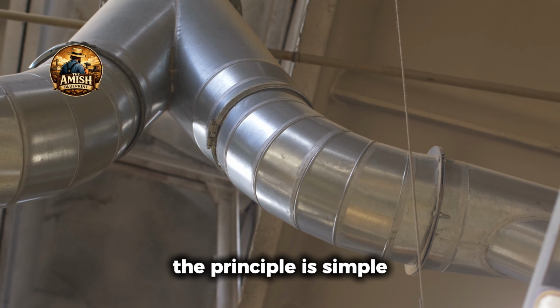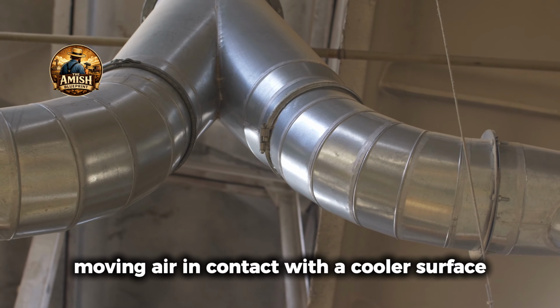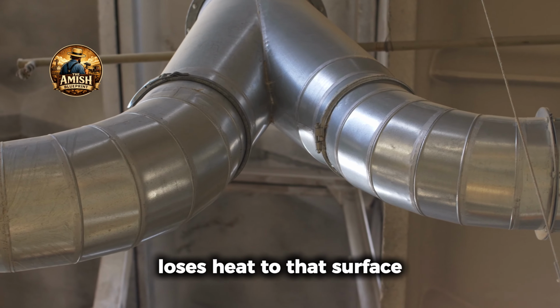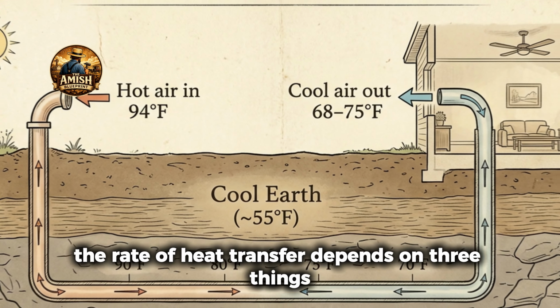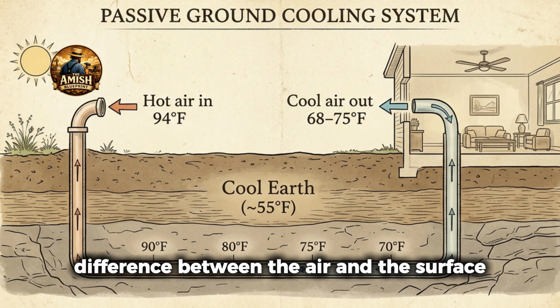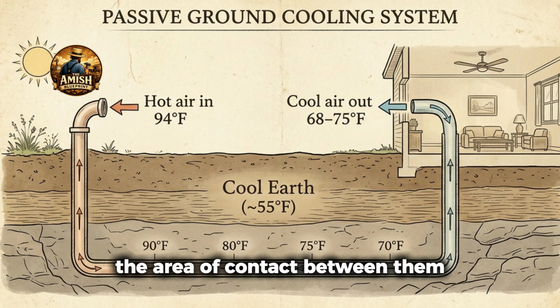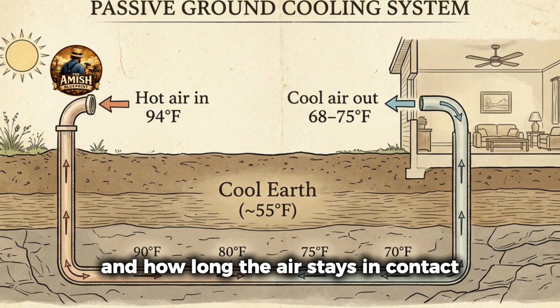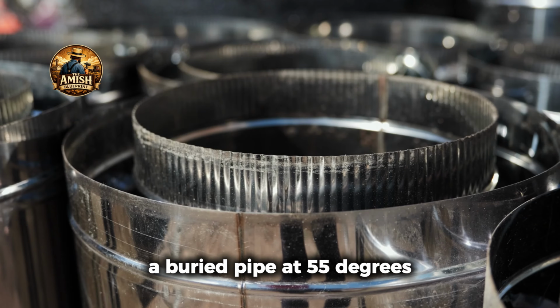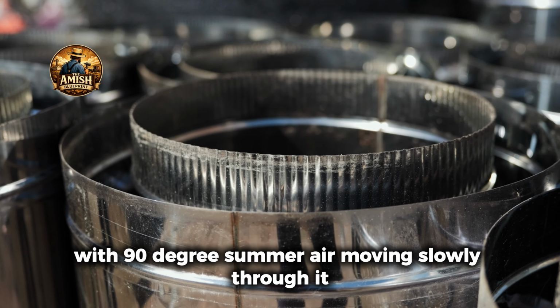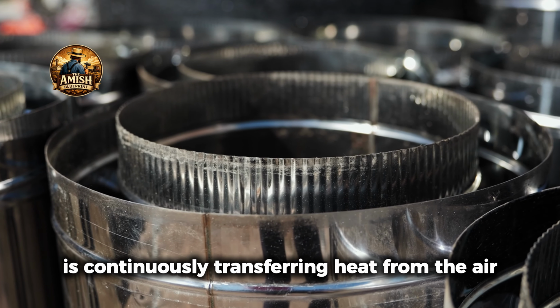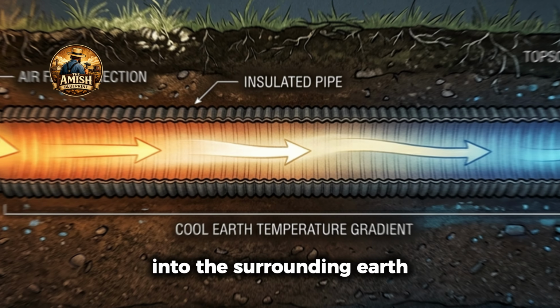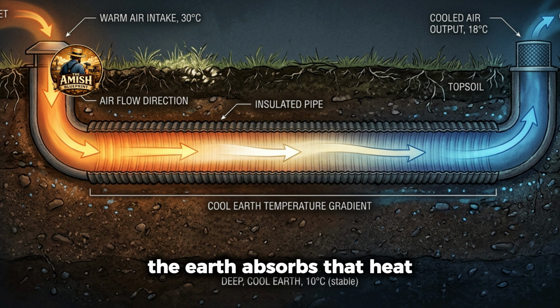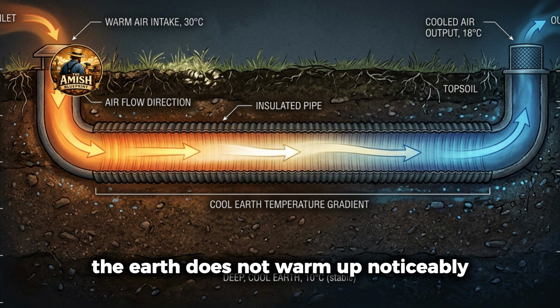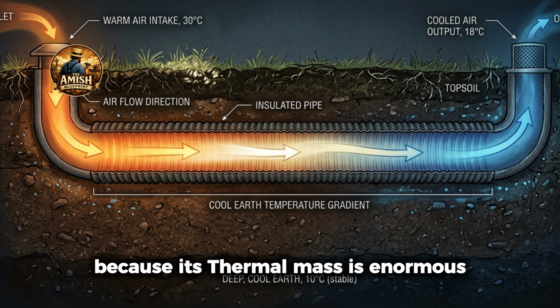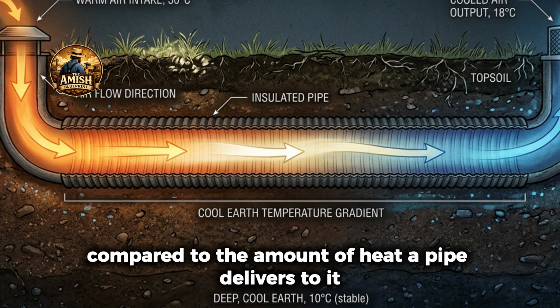The principle is simple. Moving air in contact with a cooler surface loses heat to that surface. The rate of heat transfer depends on 3 things: the temperature difference between the air and the surface, the area of contact between them, and how long the air stays in contact. A buried pipe at 55 degrees with 90-degree summer air moving slowly through it is continuously transferring heat from the air into the surrounding earth. The earth absorbs that heat. The air arrives cooler. The earth does not warm up noticeably because its thermal mass is enormous compared to the amount of heat a pipe delivers to it.